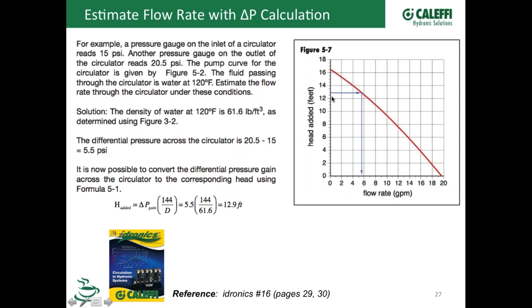So you go to the pump curve for that brand and model of pump, go up there at 12.9, run out to the curve right there, and then go straight down. And that's the flow rate that pump is moving at that condition. So we've got just under 6 gallons per minute going through that system, based on the pressure readings that we took.